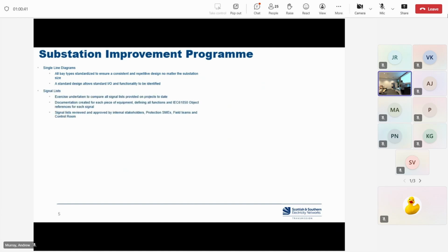In terms of signal lists, we had an equipment list of all the equipment that's approved for use within the network at the time. So we undertook an exercise to standardize on those signal lists. We compared all the signal lists from previous projects to date and found out where the inaccuracies were. Just silly things like FMP for first main protection, or the word 'first', or '1ST' - contractors may have delivered different descriptions based on the information they were using, be it from previous projects or just misinformation that had crept through.